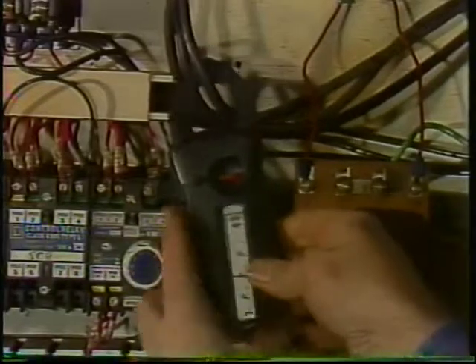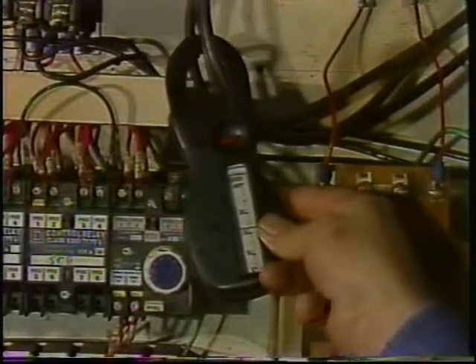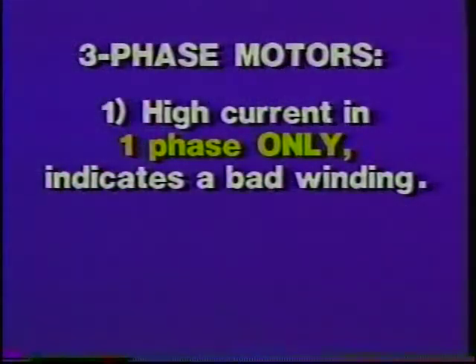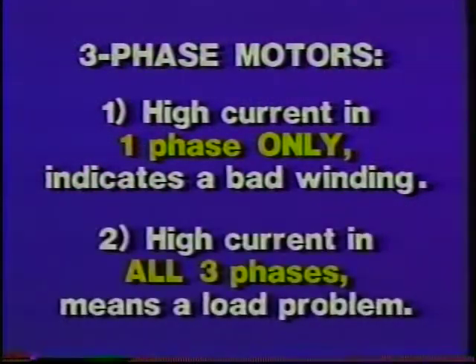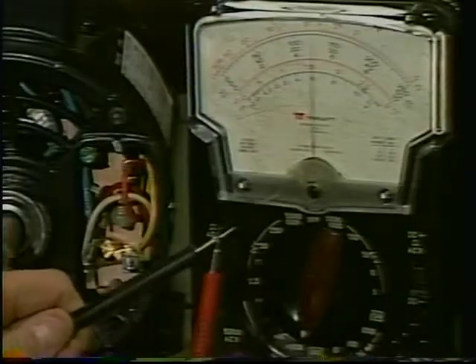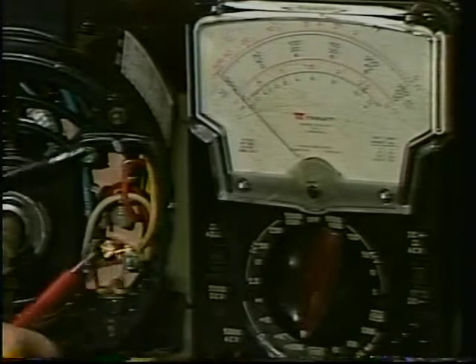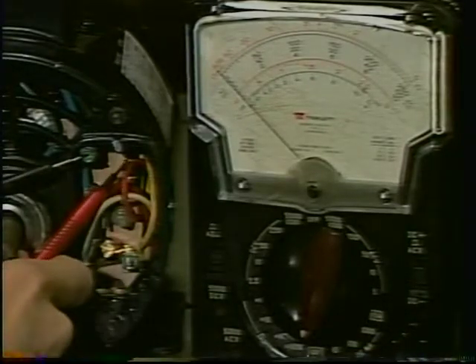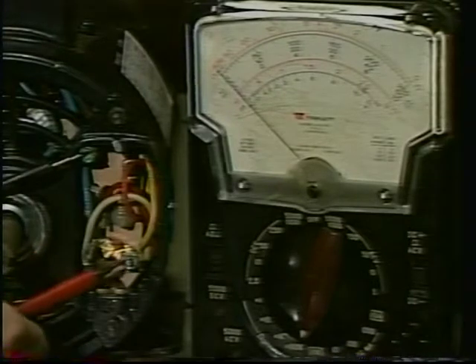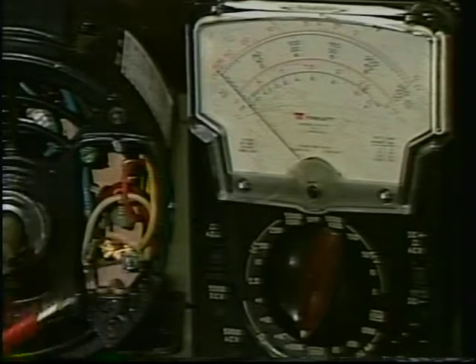If you are troubleshooting a three-phase motor, you may already have one important piece of evidence. When you check the current draw of the motor, were the currents in all three lines exactly equal? On a three-phase motor, high current in one phase only usually indicates a bad winding. High current in all three phases means a problem in the load. In a single-phase AC motor or DC motor, all you can do in most cases is to check the motor for shorts to ground. Shorted windings, as we said, probably will not show up.